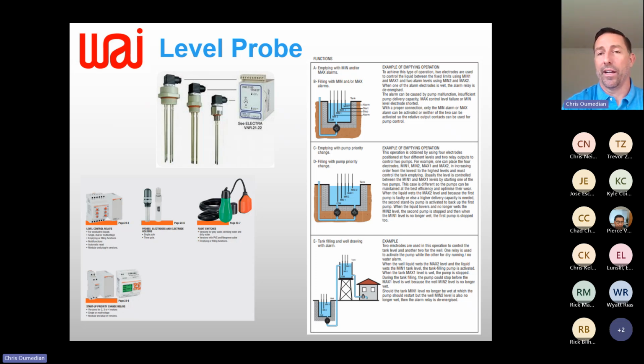There's some pictorials on the right that kind of go through. Looks like we've got one over here with 4 or 5 probes, a couple with 3 here, high, low, mid. And this is just basic tank level monitoring, very inexpensive way to do tank level monitoring. And then you've got some interpretation devices that will take those outputs and turn it into a transistor, a relay, perhaps a Modbus or Ethernet register output value at that point. Questions on level probes?